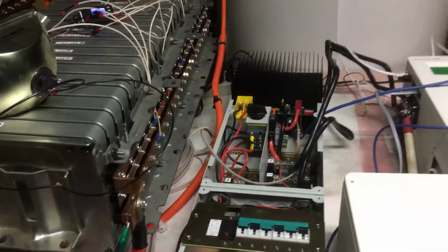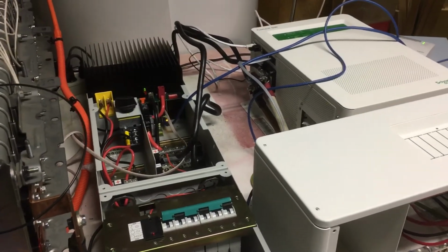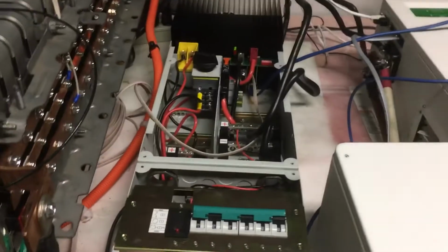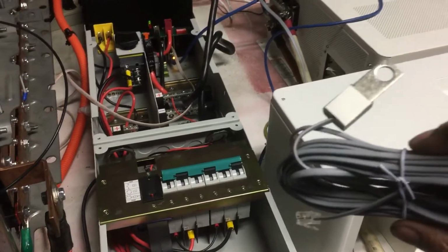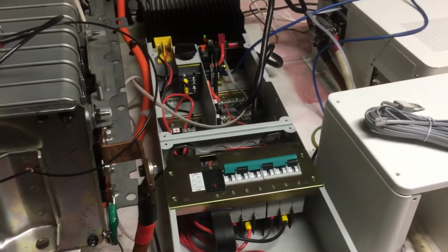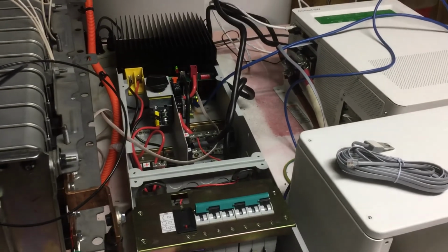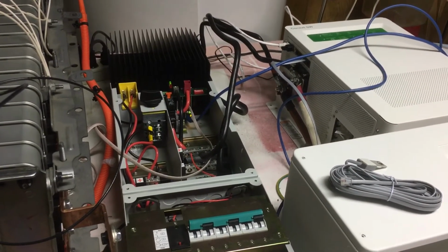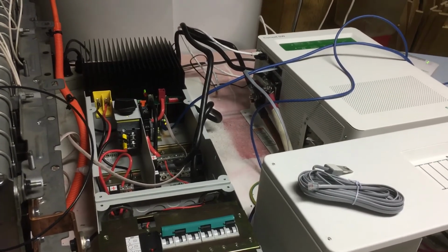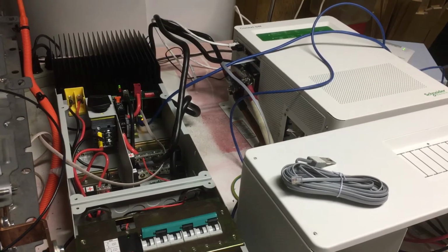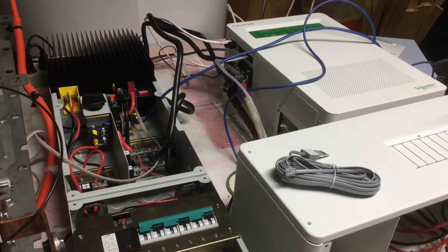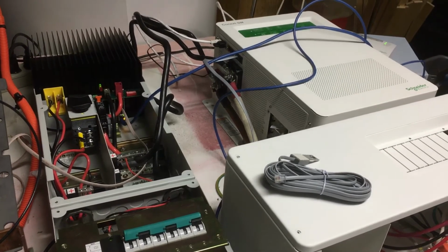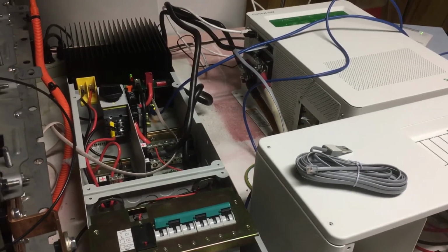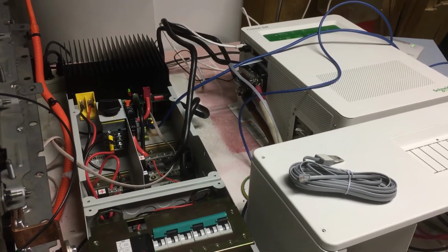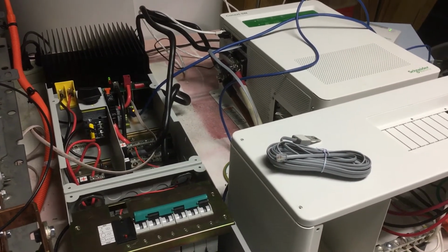Speaking of charge enable, I have been playing around with a trick using the battery temperature sensor—that's what this guy is here, also on a phone cord port for the Schneider. Basically, room temp seems to be about 11 kiloohms. If you open that up, nothing happens, but if you short across that 11 kiloohms, that will send the charger into a fault mode which will disable it. It's not maybe the cleanest way to shut it down, but it's certainly a way to do it. So that's one of the things I'm looking at for how to shut the charger down.